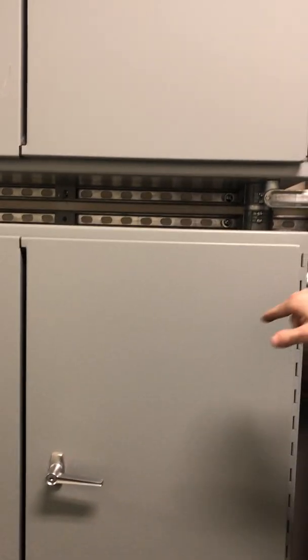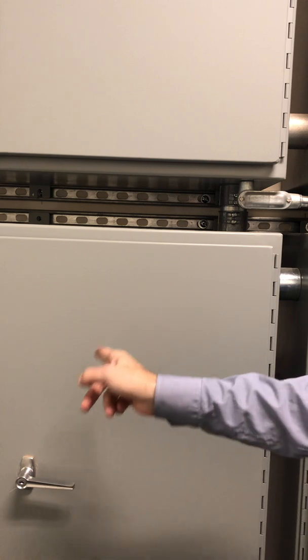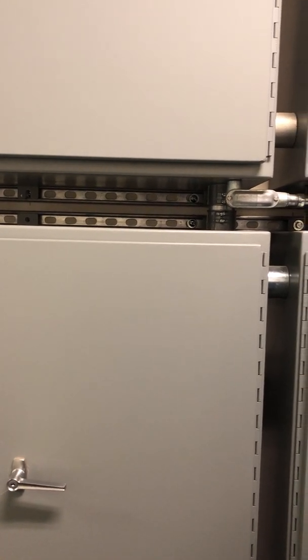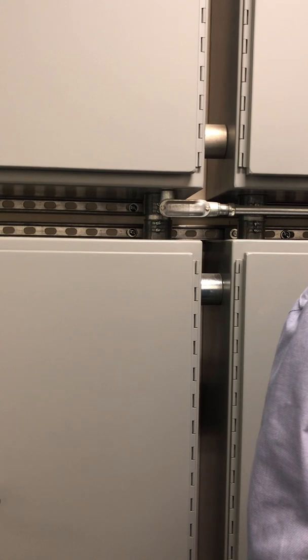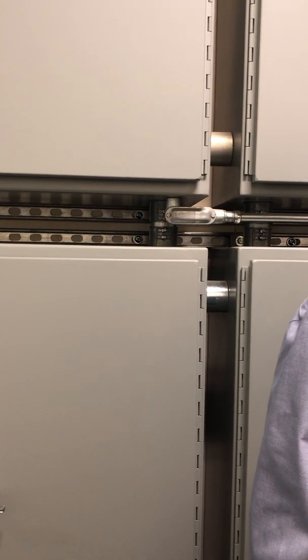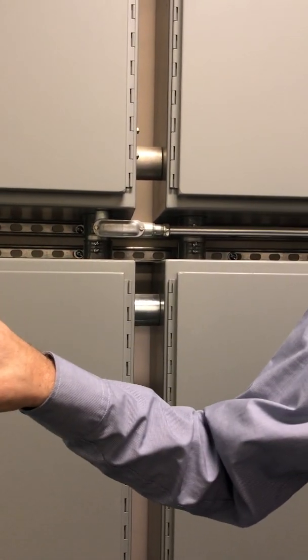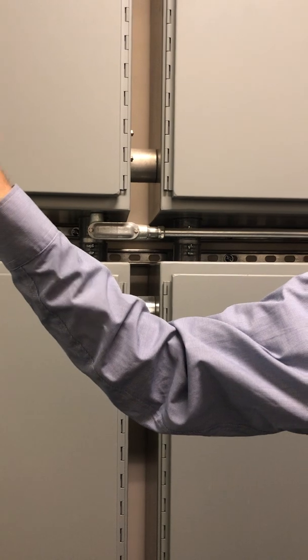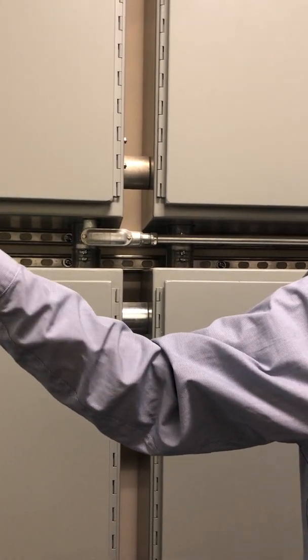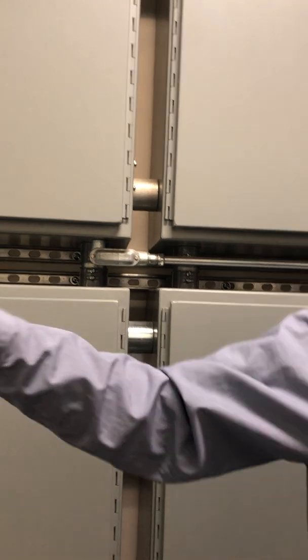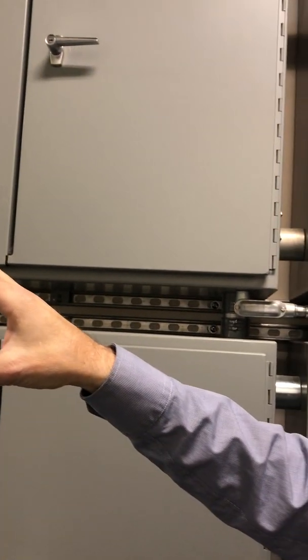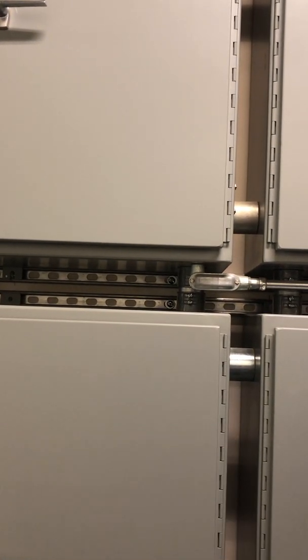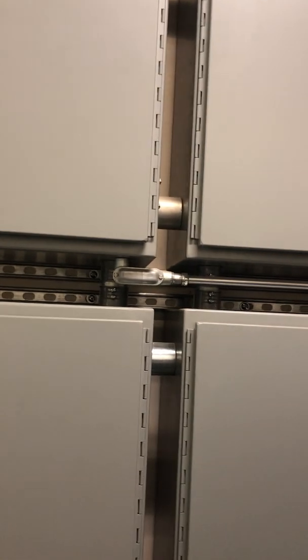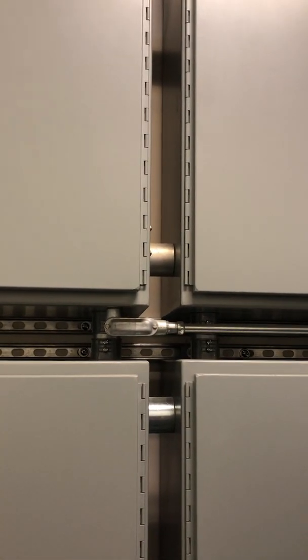Basically, it's 3 occupied cabinets and 1 for expansion. In the larger design, we were going to segment each row as its own secured zone to run off the card readers. The card reader system works right now—it just needs its own standalone software, a computer badge printing end, and a software license to operate. We left all the card readers intact and operational, but since we don't have the software, that's why we're going around on card keys. It's not a large undertaking, and the contractor who installed it is here locally in the valley.